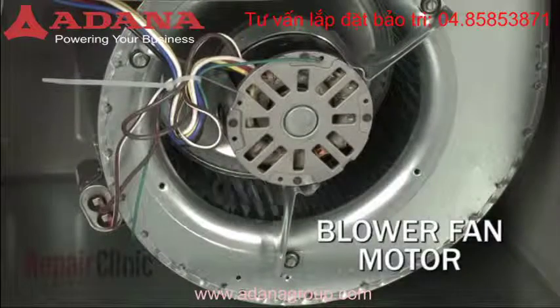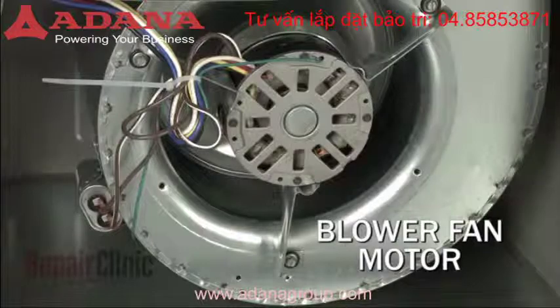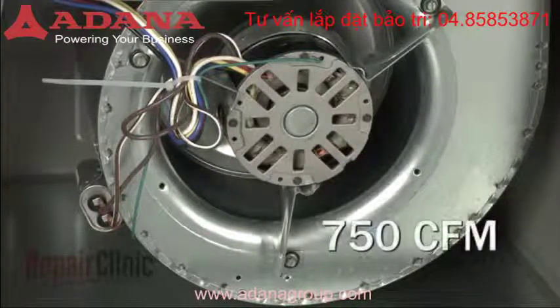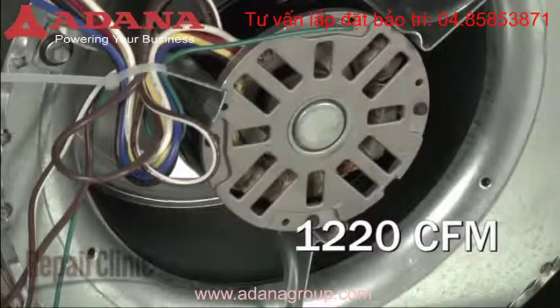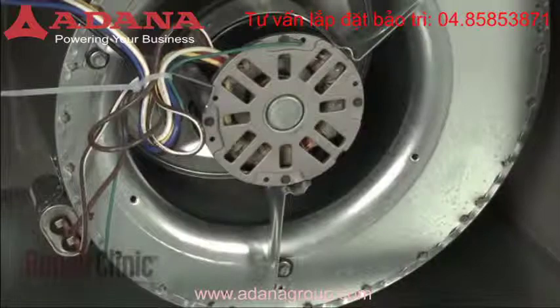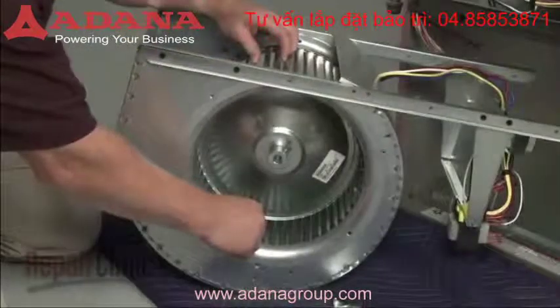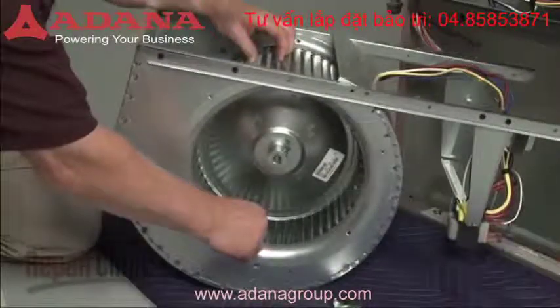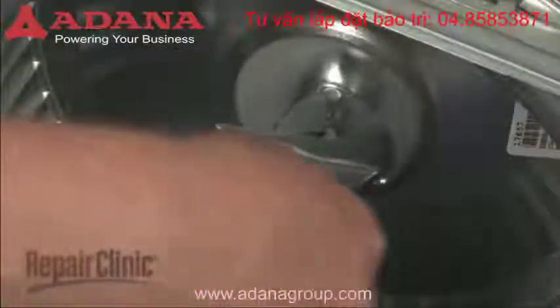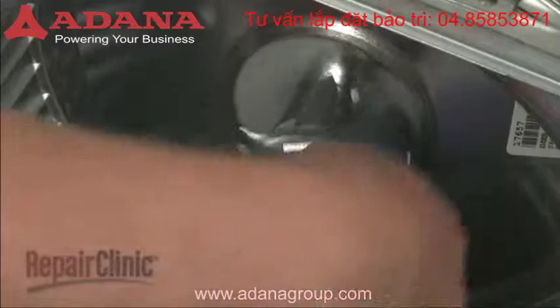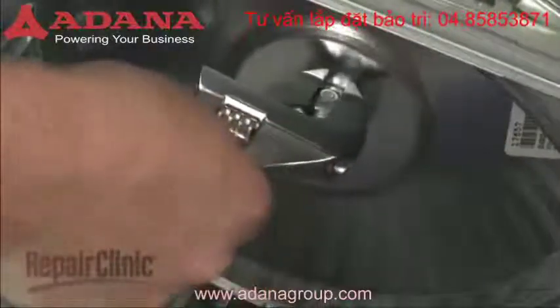The blower fan motor can run at multiple speeds to improve efficiency. Lower speeds are used when the furnace is heating, and higher speeds are used for air conditioning. If the circulation blower fan becomes noisy during use, the set screw on the blower wheel may have loosened, causing the wheel to wobble on the motor shaft. You can fix this problem by tightening or replacing the screw, or replacing the blower wheel altogether.